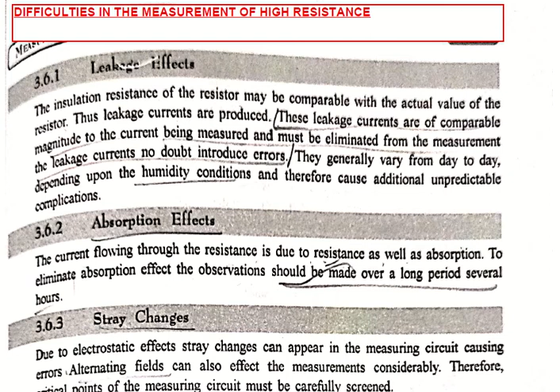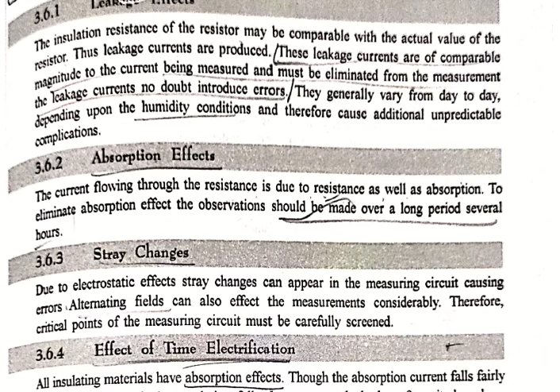First one is leakage effect. The insulation resistance of the resistor may be comparable with the actual value of the resistor. We have seen this in our Megger method. So leakage currents are produced. These leakage currents are of comparable magnitude to the current that is being measured. So this leakage current should be eliminated from our measurement devices, because it will introduce errors, and generally they vary from day to day depending upon the humidity conditions, and it may depend upon some other factors also.